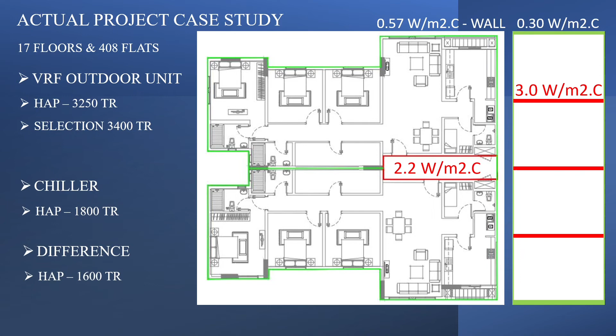Surprisingly, there is a difference of 1600 TR. Capital cost analysis. Usually, people in the industry compare a 3250 TR VRF system to a 3250 TR chiller plant. Here, they claim that there is a price difference of about 2.1 million US dollars. Even though the VRF system has many drawbacks over the chilled water system, the client will be forced to go for the VRF system. Applying this new design concept, the 3400 TR VRF system should be compared to the 1800 TR chilled water system.